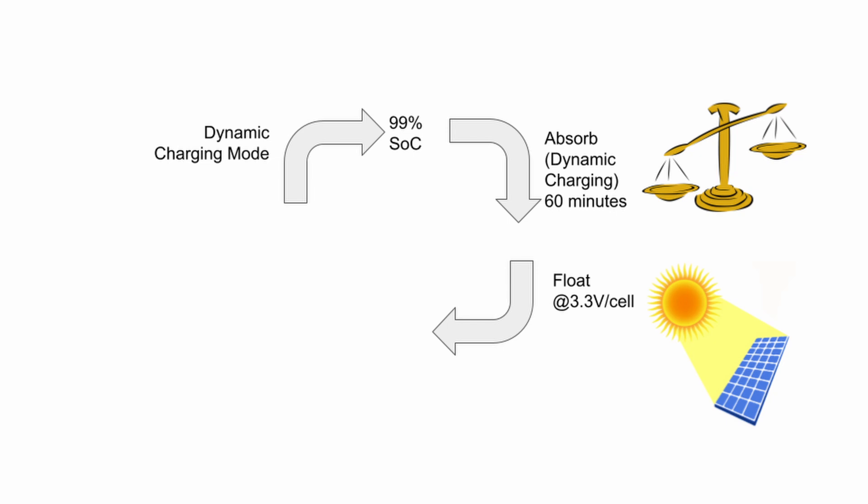Finally, once both absorption and float modes are elapsed, the charger would be told to stop, supplying zero voltage and zero current. You can of course disable either the absorb or float stages entirely by just reducing the time down to one minute. The charger would then be told to stop on a fully charged battery.